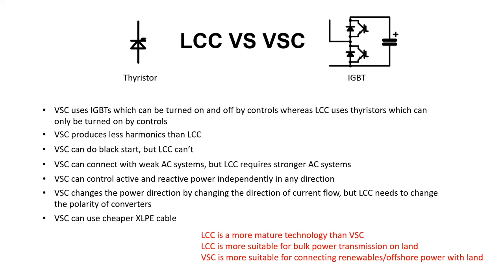VSC can control active and reactive power independently in any direction. With VSC, when it comes to changing the power direction, it requires a change in the direction of current flow, whereas with LCC, we need to change the polarity of the converters. And VSC uses cheaper XLPE cables, whereas LCC uses expensive MI, mass impregnated cables.